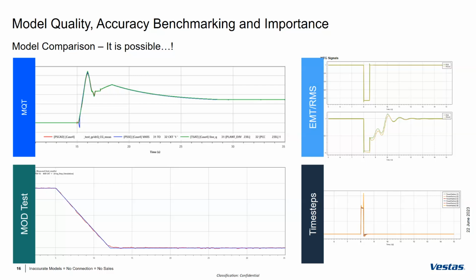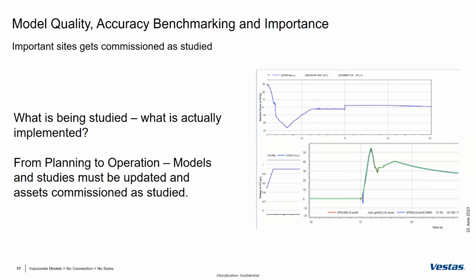Next slide. One of today's challenges is that a detailed model doesn't always mean an accurate model, and also what's being studied versus what's implemented on site. On the right side, it's a fault ride-through event that's fed in. The expected behavior is the green curve on the bottom right, showing reactive power injection. What was actually commissioned and installed at the site was the blue curve, and there's about a 60 megawatt difference in the actual plant response.